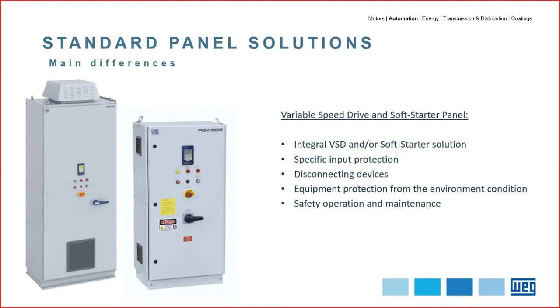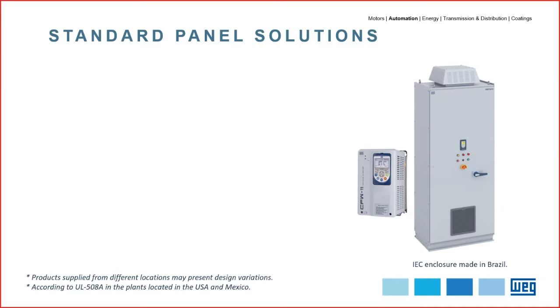the complete enclosure protection. A VSD panel or a soft starter panel is equipped with monitoring equipment directly on the panel door. This is also useful for a better visual status diagnostics and control of the process running by that equipment. All the listed points are just some examples of the reasons to consider a VSD or a soft starter panel for your application. Following these main listed points, we can briefly present the available standard panel solutions and their most relevant characteristics.